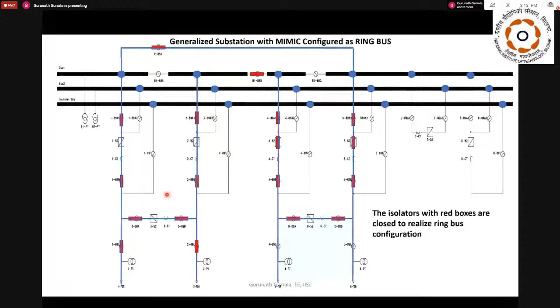That means all the other things which are not highlighted, you cannot turn on or turn off. Basically in the ring bus, I have one feeder here, one feeder here. You can see between 2 feeders, you will have a breaker, so this breaker and this breaker. Similarly for this one, you have this breaker and this breaker, and this goes through this particular bus. Again, this breaker is completely blocked, so for this particular feeder you have this breaker as well as this breaker, which need to be operated. This is almost like a double breaker scheme. Here 2 breakers will be there, but you will always be sharing a breaker with the other feeder too.